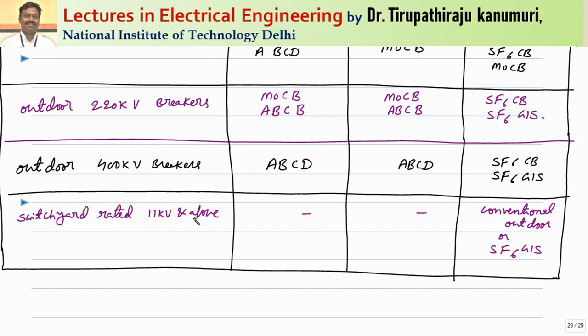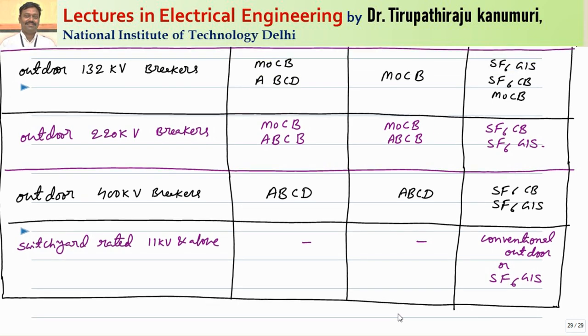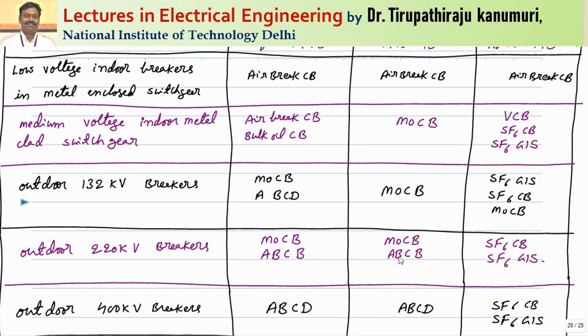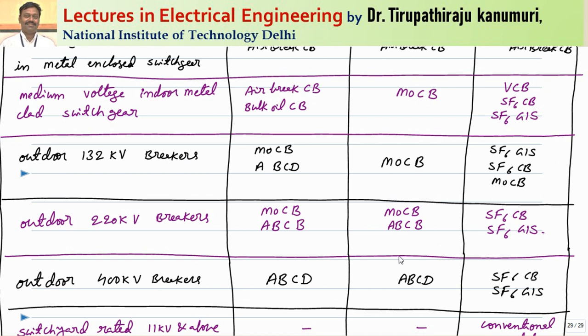For switch yards rated 11 kV and above, they can be either conventional outdoor type substations or nowadays gas insulated substations using SF6. By using SF6 GIS, the size of the substation decreases drastically because the clearance required between parts decreases significantly. To summarize: the current trend is to use air break circuit breakers only for low voltages, and for medium or high voltages, vacuum or SF6 circuit breakers are used. In very few applications, minimum oil circuit breakers are used where frequent operations are not required.